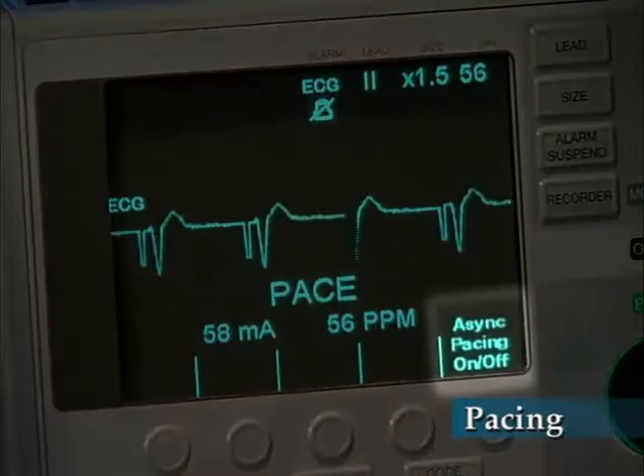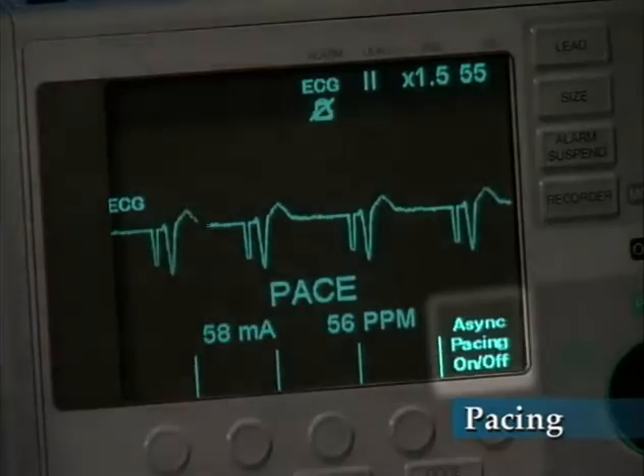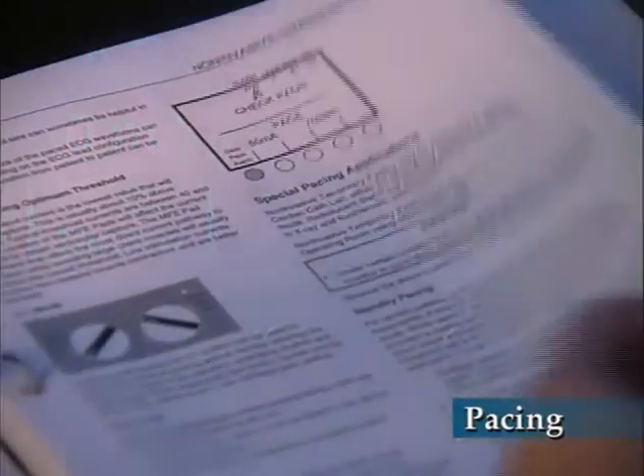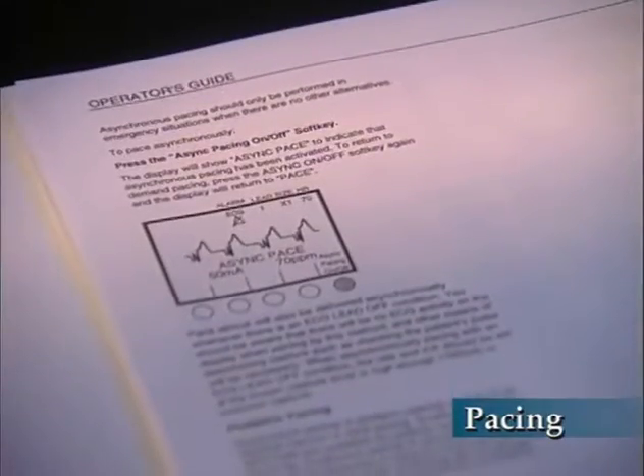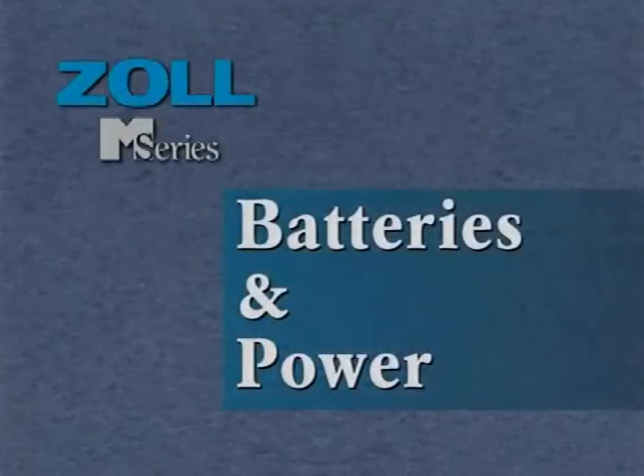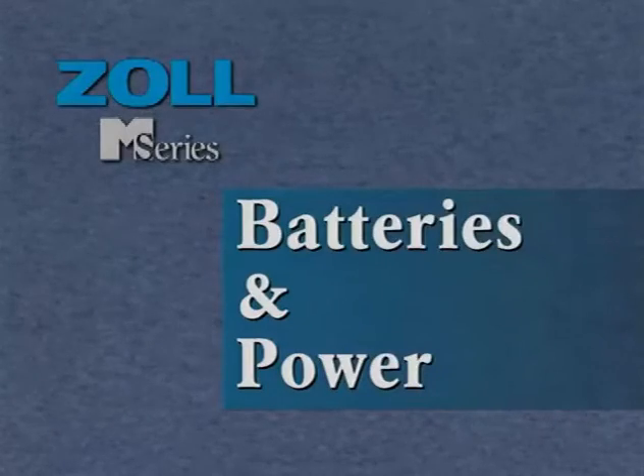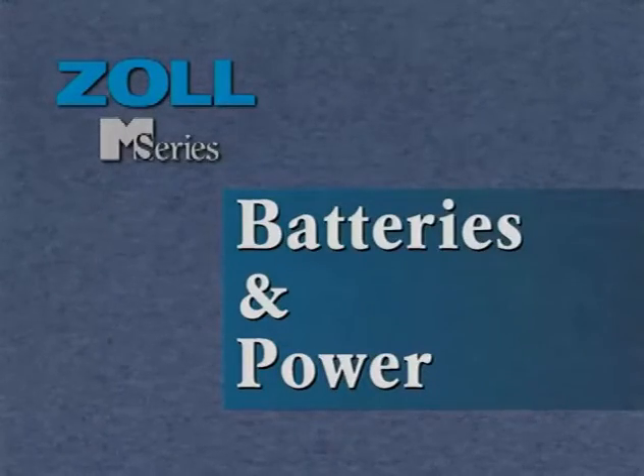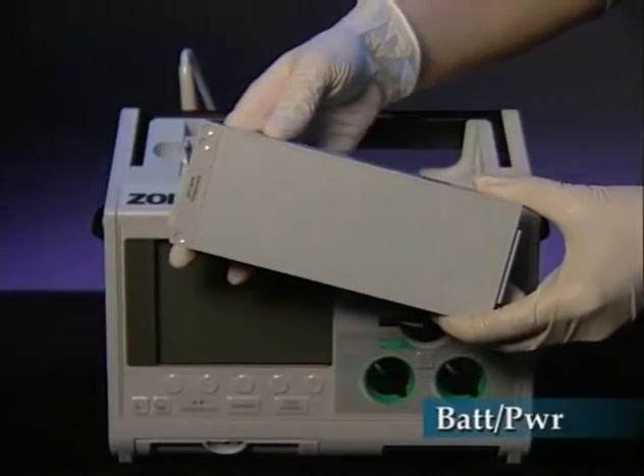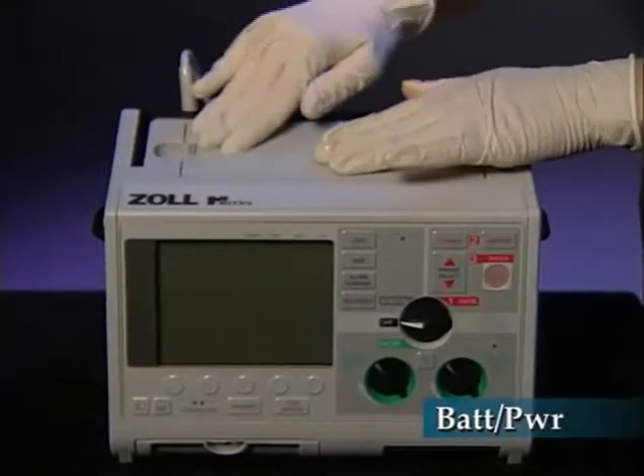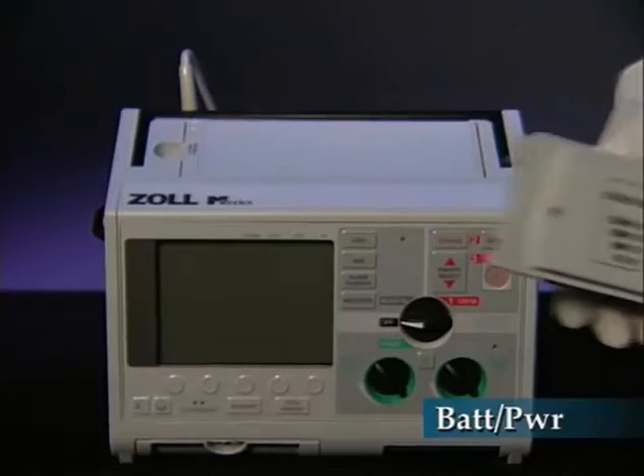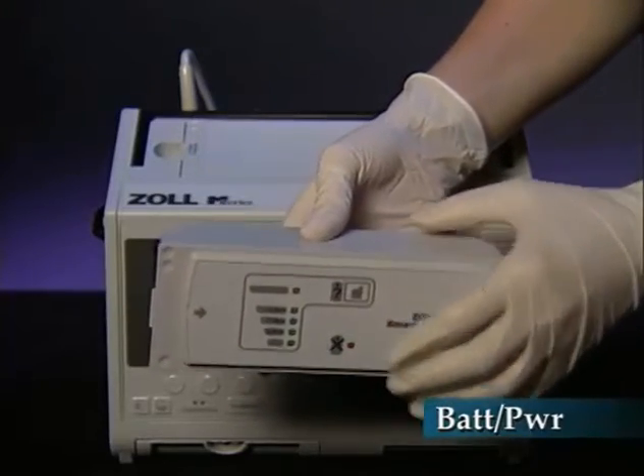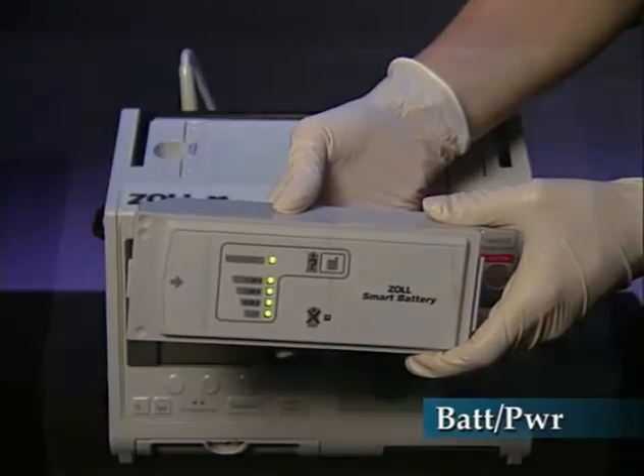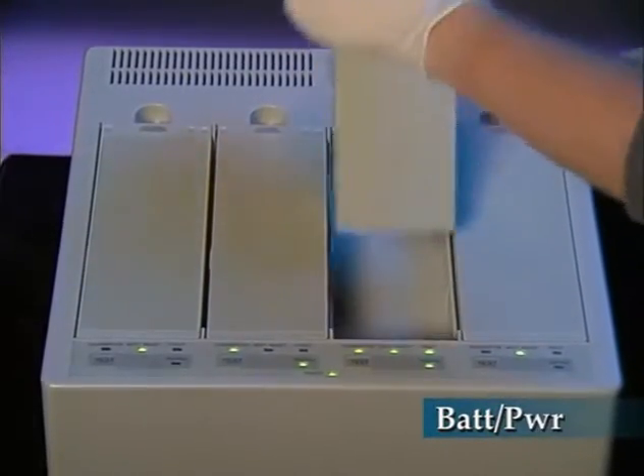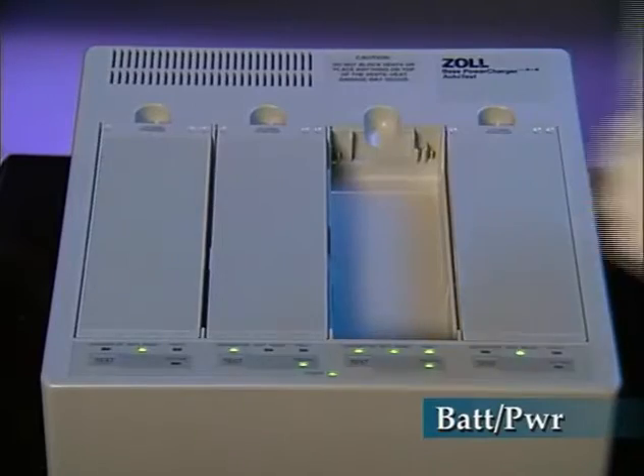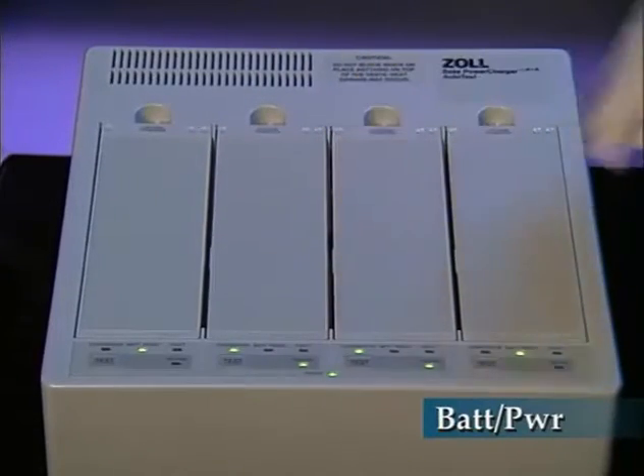The M Series also incorporates an asynchronous capability that is selected using a soft key. The operator's guide has additional information on this feature. The M Series can operate from batteries, AC power, or DC power, and uses a rapidly replaceable battery pack. Two types of replaceable battery packs are available. One is a standard battery pack, and the other is a smart battery pack with capacity indicators. Batteries can be charged within the unit or by using an external battery charger. ZOLL recommends a separate battery charger be available to charge spare batteries and perform periodic testing.